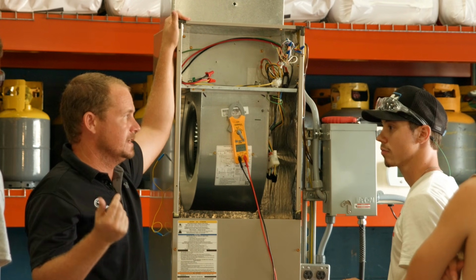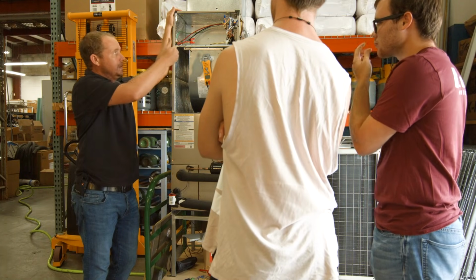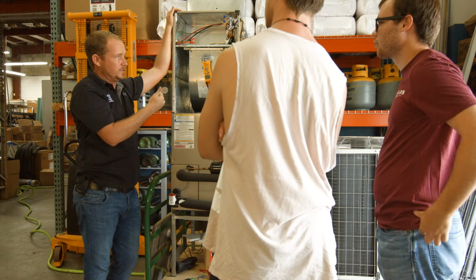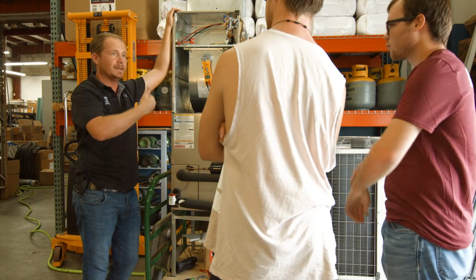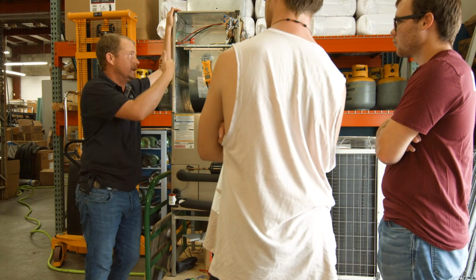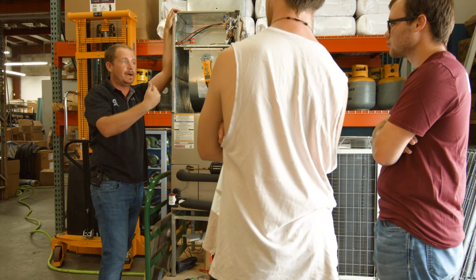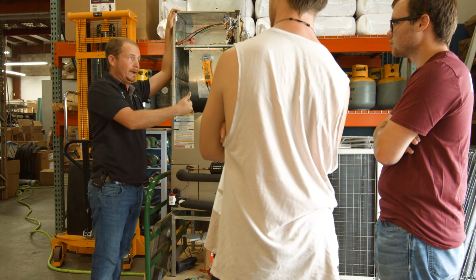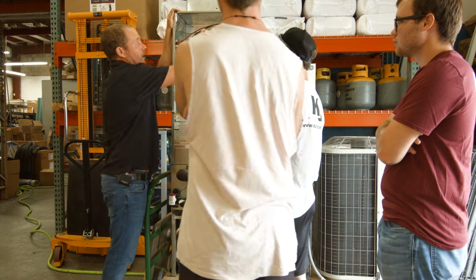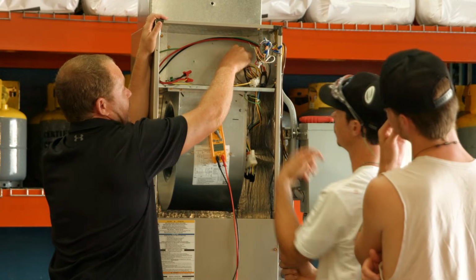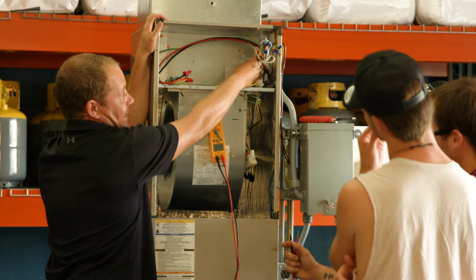or is it actually that conductor? So in this method, we disconnected from the transformer, so we're not using voltage, we're doing it de-energized, using the ohm meter, and now we're measuring a low ohm path between G and ground, specifically because on this transformer, G and ground are bonded together. They're connected together.